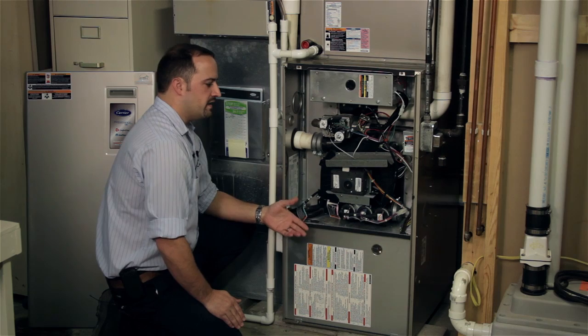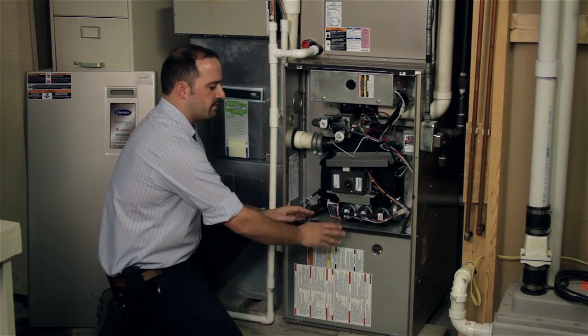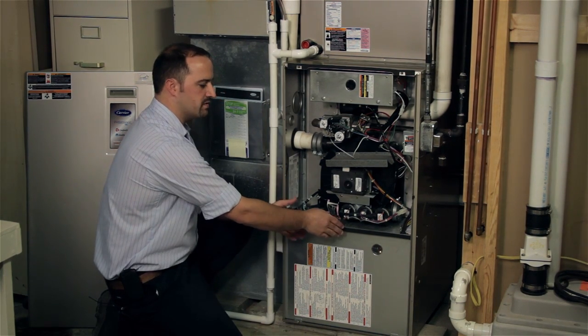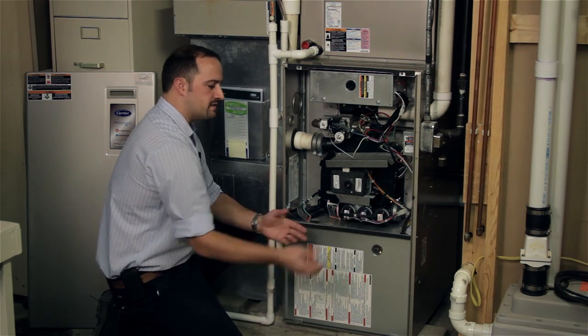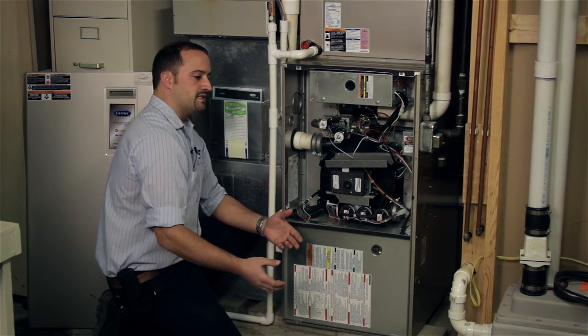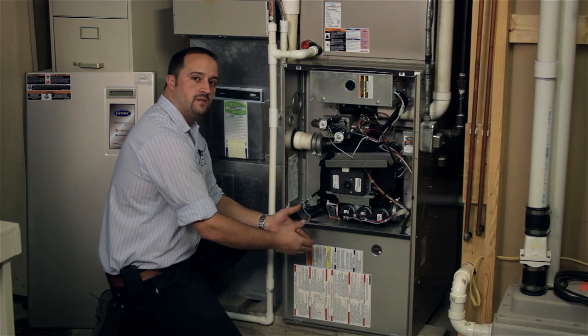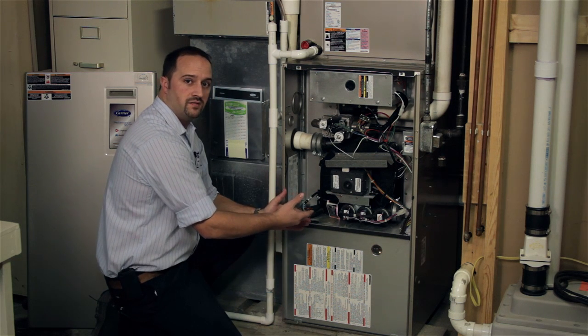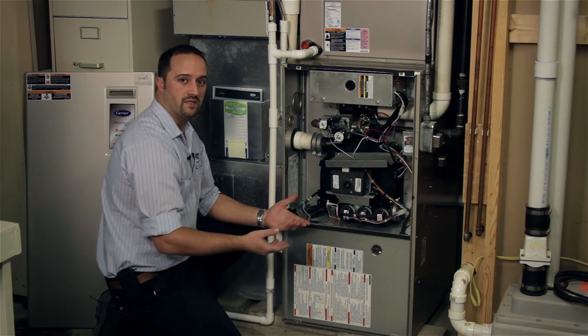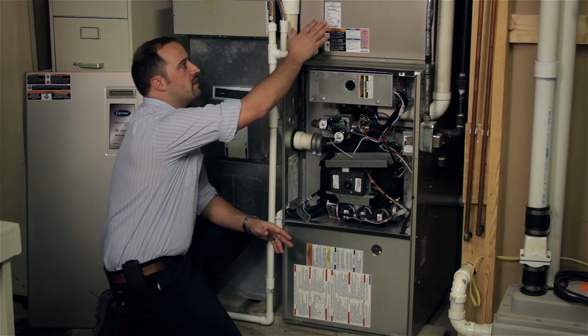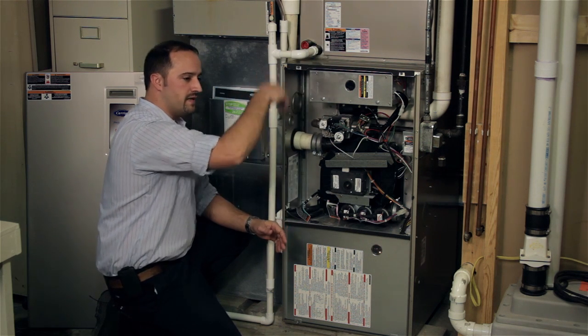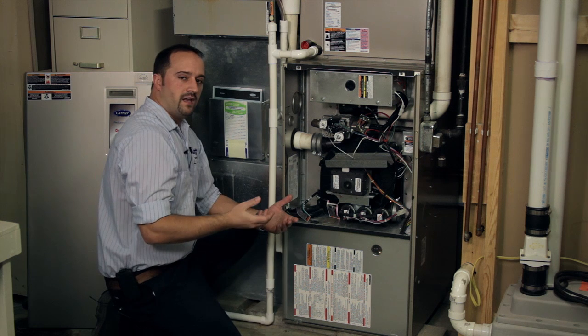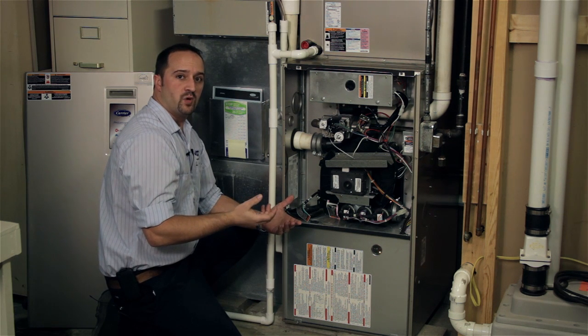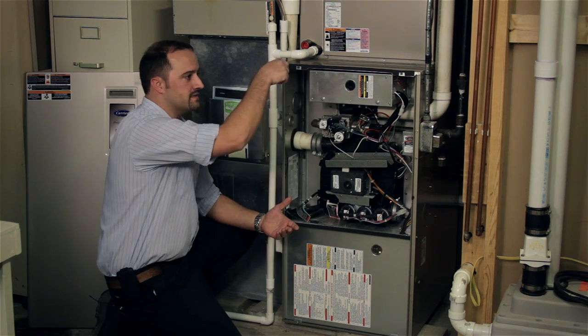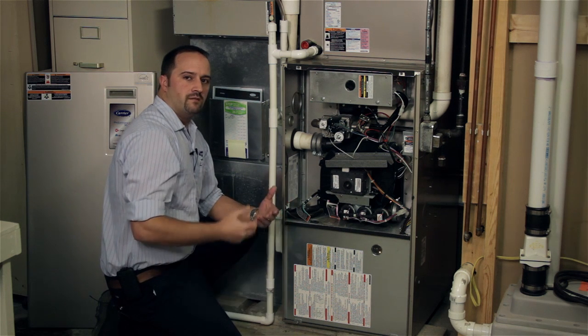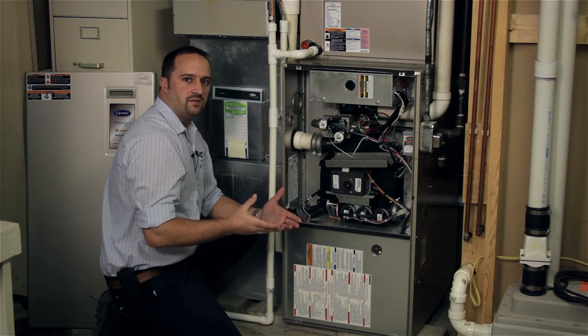After that, he's going to get really in-depth into it. He's going to pull the panels off, take them out of the way. In this case here, there's a blower compartment, a big blower motor. He'd slide that out of the way. A lot of guys will actually crawl inside your furnace to look up inside at the heat exchanger to make sure there's no cracks or popped rivets, things of that nature. They may also take off the top panel and look down. Some guys will have a borescope, just a little camera on the end of a flexible wand that they can stick inside. The whole goal is to really inspect that heat exchanger to make sure there's no cracks in it.